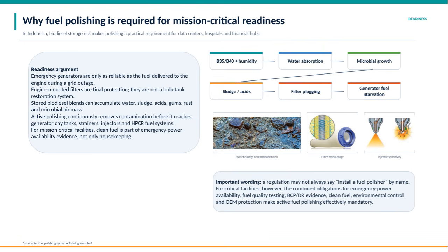Active fuel polishing systems continuously clean the fuel, removing contaminants before they reach the generator's day tanks and sensitive components like strainers, injectors, and high-pressure common rail systems. For critical facilities like data centers, hospitals, and financial hubs, maintaining clean fuel isn't just about good housekeeping. It's a vital part of demonstrating emergency power system readiness. Regulations may not explicitly require installing fuel polishers, but the combined demands of fuel quality, environmental control, equipment protection, and business continuity planning make active fuel polishing a practical necessity in ensuring reliable operation when it matters most.